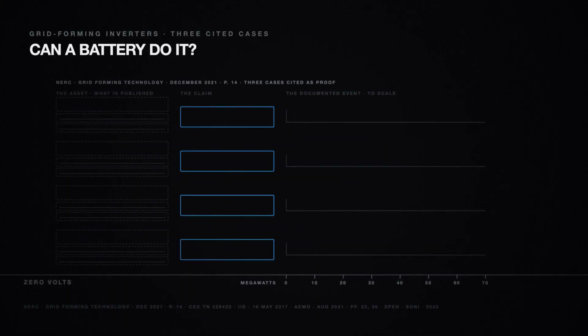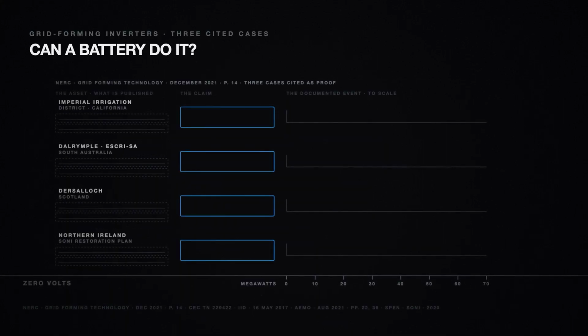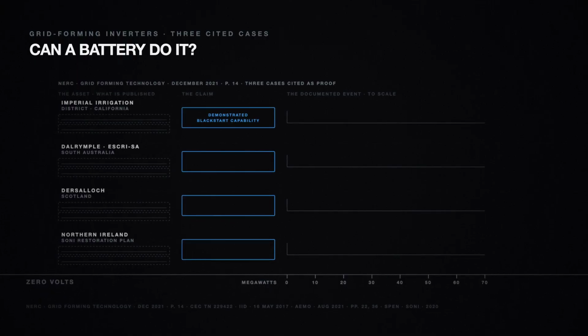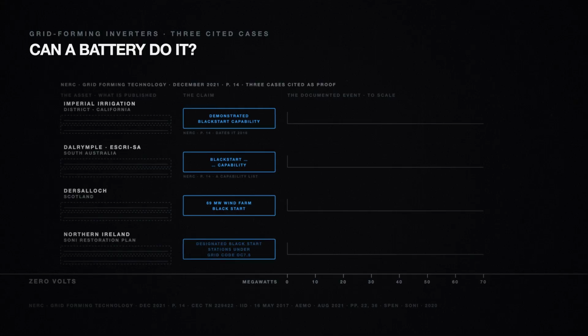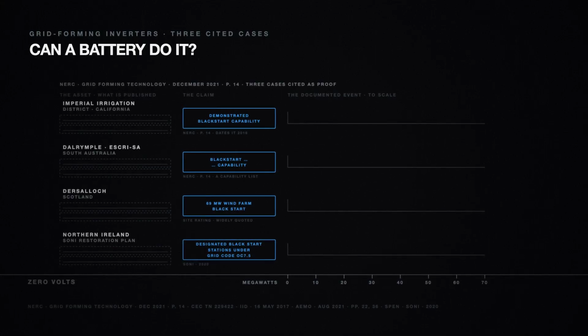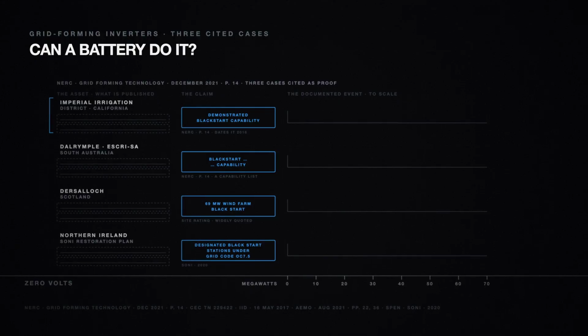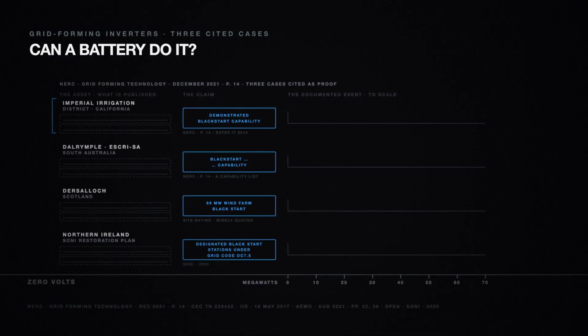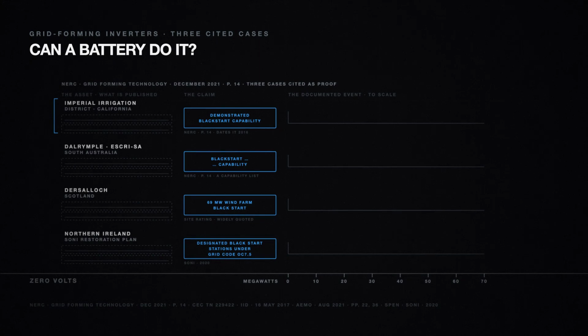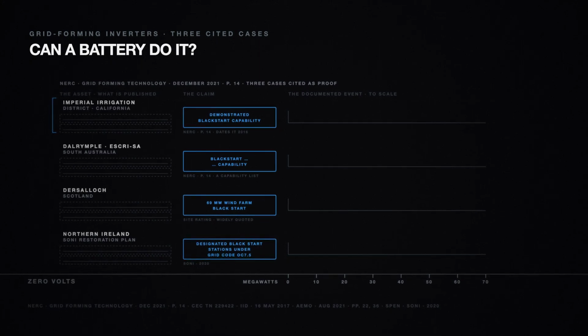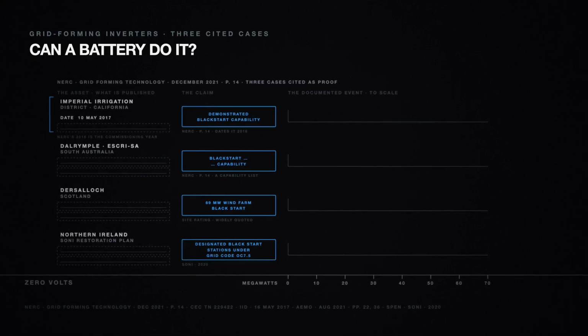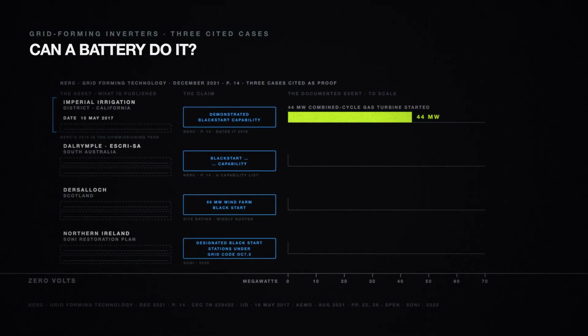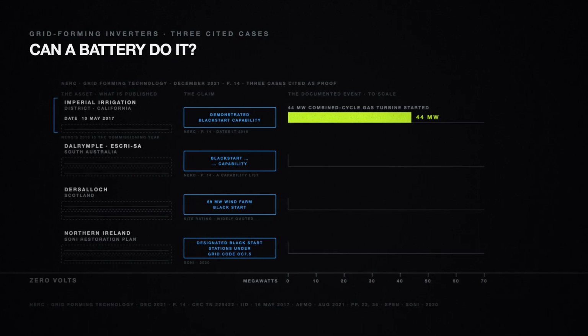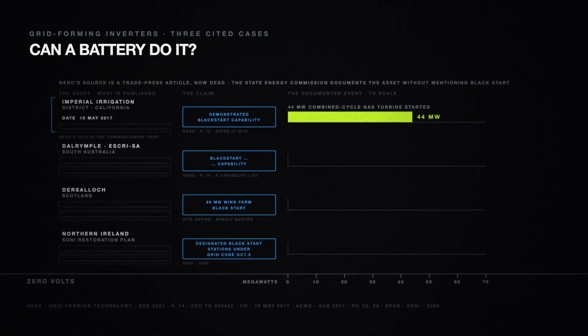A modern answer gets the same test. The Reliability Organization's white paper on grid forming technology says such inverters can be designed as an initial black start resource. 3 cases are cited as proof. First, the Imperial Irrigation District in California. The white paper dates its battery's black start to 2016. That is the commissioning year. The event was the 10th of May, 2017, when the battery started a 44 megawatt combined cycle gas turbine. A real event, and the thinnest paper trail here.